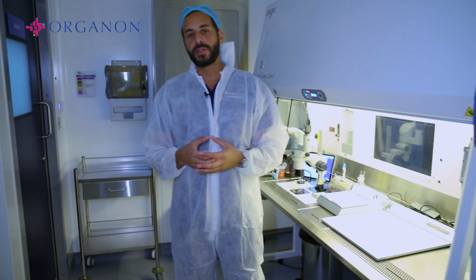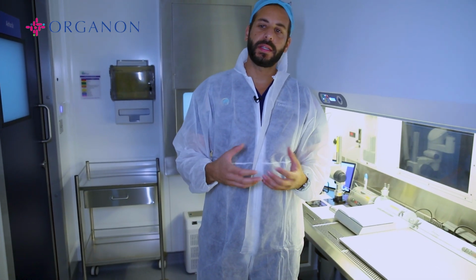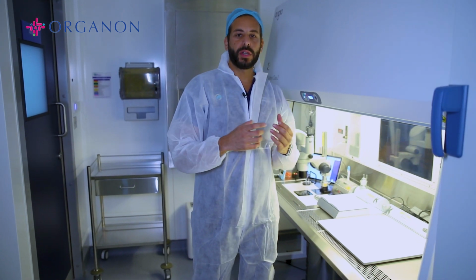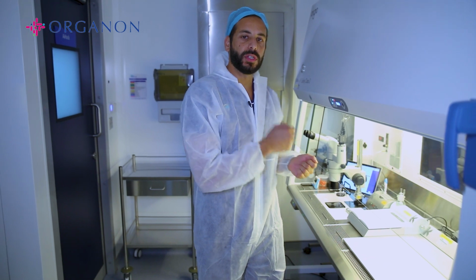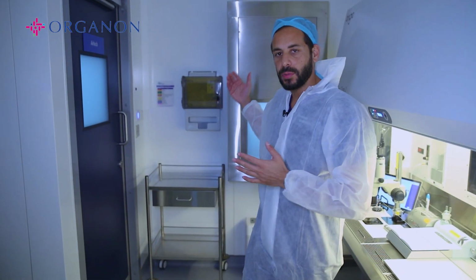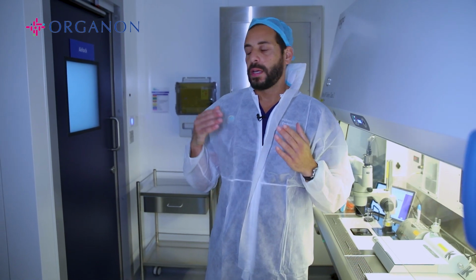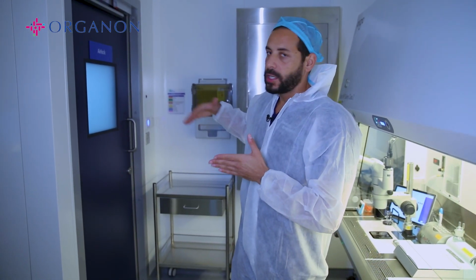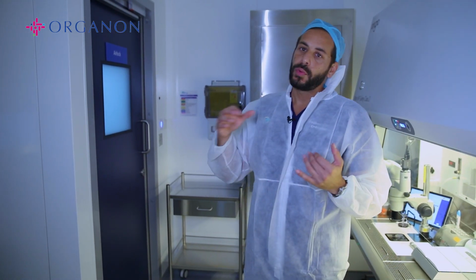Embryo transfer procedure is an extremely delicate and sensitive procedure. In order to minimize the time where we have the embryos outside of the incubators, from the moment we do the loading inside the catheter until we give it to the physicians or perform the transfer itself, we have created this airlock system between the IVF lab and the OT. So we maintain the correct and needed pressure, and at the same time, we reduce the time.